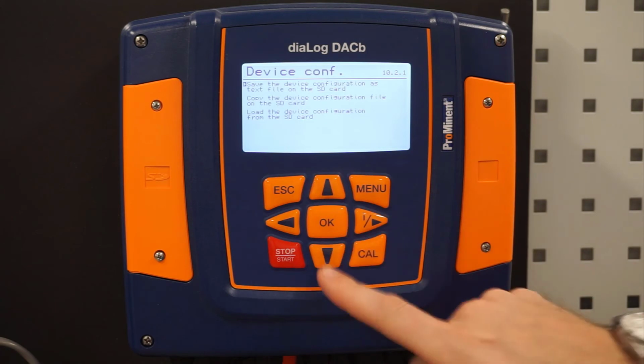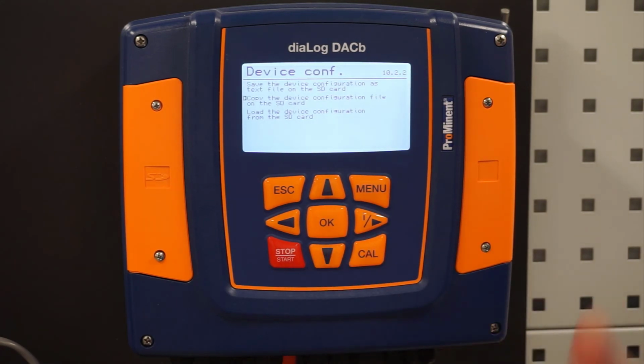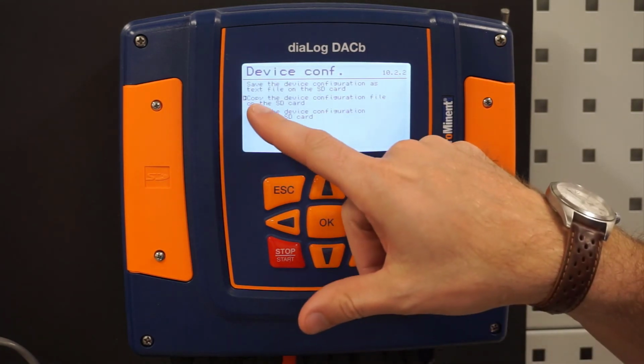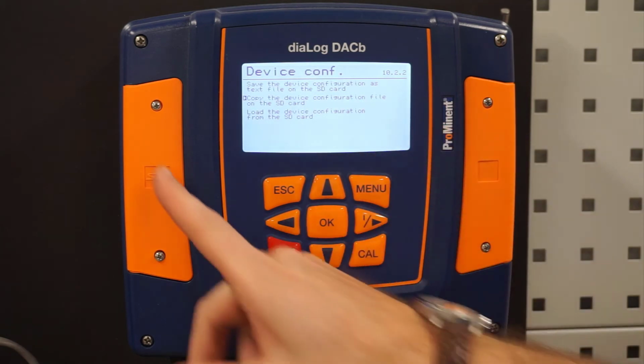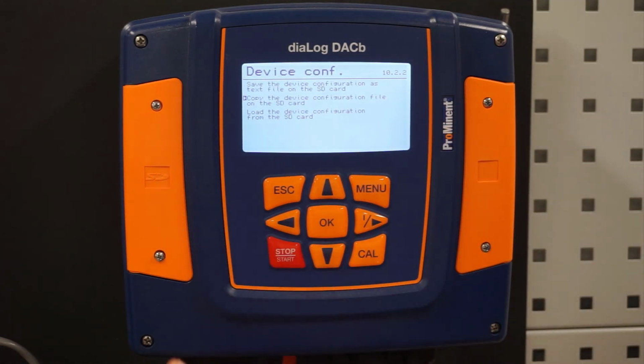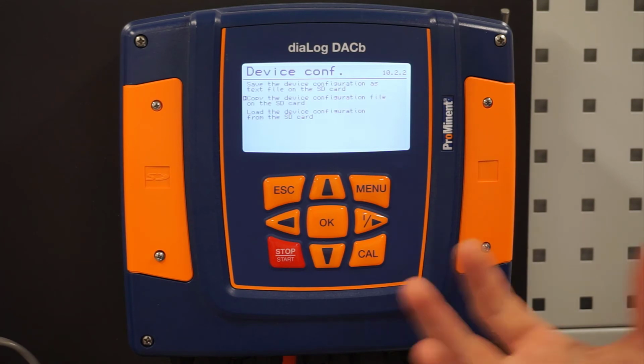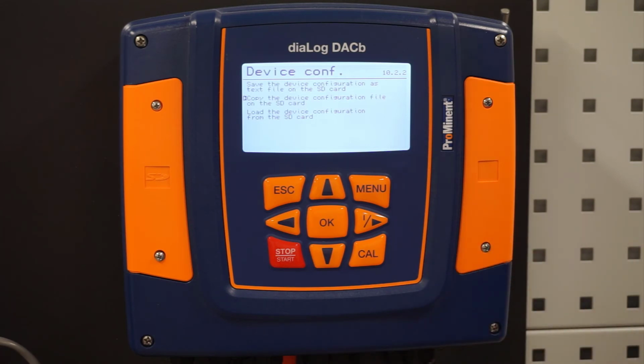The more important thing is, I would suggest after you're done programming the controller, copy the device configuration to the SD card. You can just leave it on there. I would also maybe recommend taking that SD card out of there and copying that file into maybe a folder on your computer. That way you have that configuration always there. If, for instance, somebody were to come here and accidentally change a whole bunch of settings, not really knowing what they were doing, you would have that file on your computer.